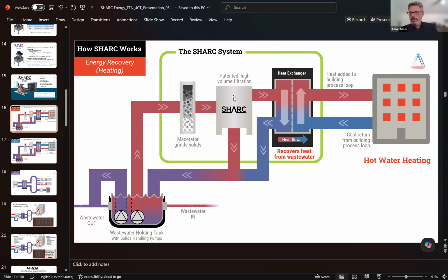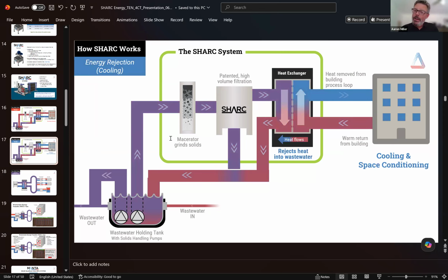In this operation, we're taking heat from the wastewater, mixing it into the building process loop via the heat exchanger. I've reversed the flow of the SHARC, and now I can take rejected heat from your chiller plant, right? Instead of sending it up to a cooling tower, send it down to the SHARC, and I can take the heat out of that chilling loop, mix it into the sanitary, and flush it down the toilet. So heat source, heat sink, just like geothermal.